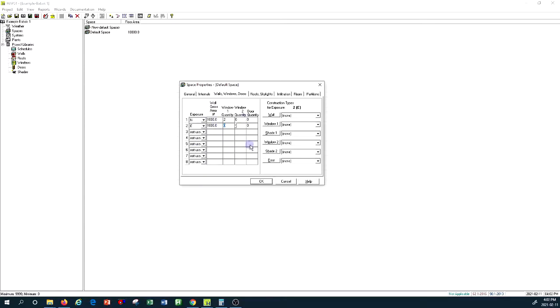That's how you determine the exposure side of your space and all the building envelope requirements. Remember that we first have to build a library of all types of windows, doors, and walls for the building so that we can select them from the drop-down menu. This tab is exclusively for your space-identified building envelope components. The idea here is to calculate the conduction heat rate, which is based on the equation: Area multiplied by the U-value (coefficient of heat transfer) multiplied by the temperature difference.